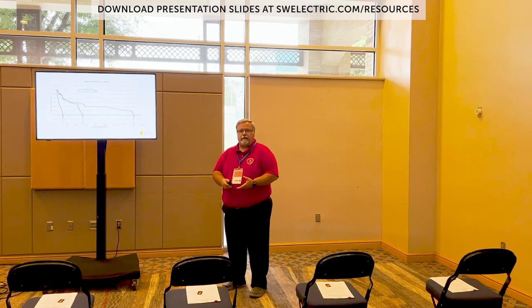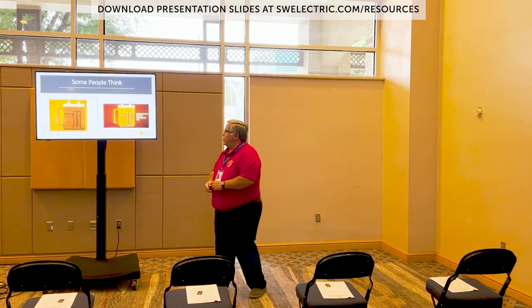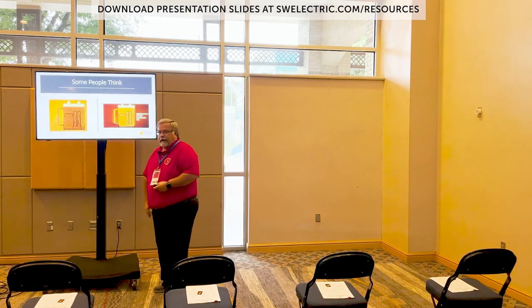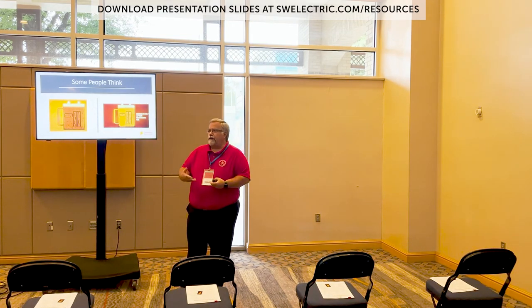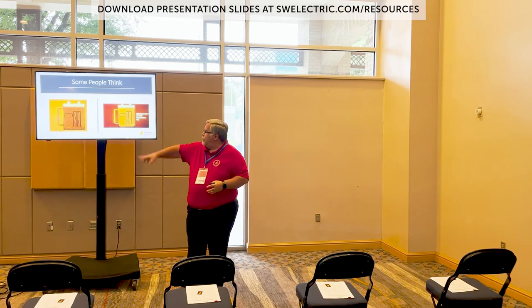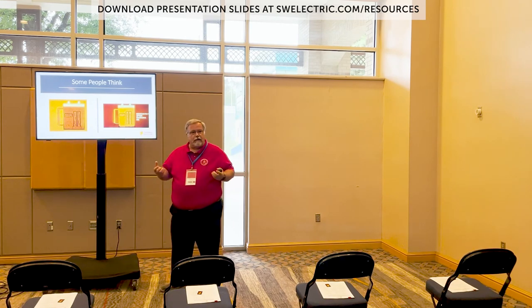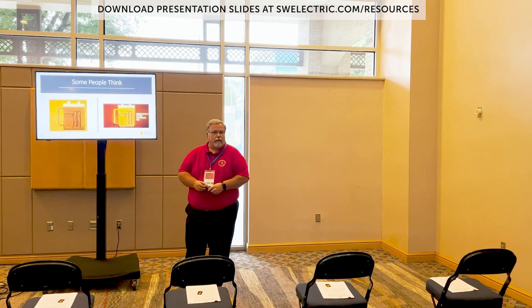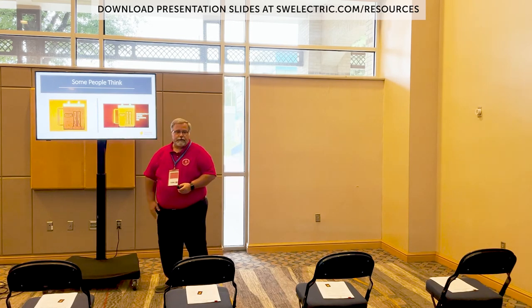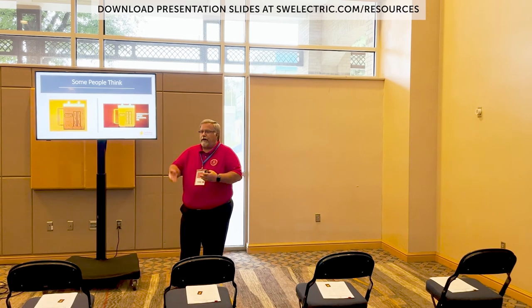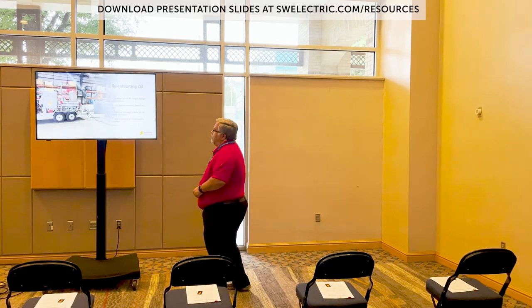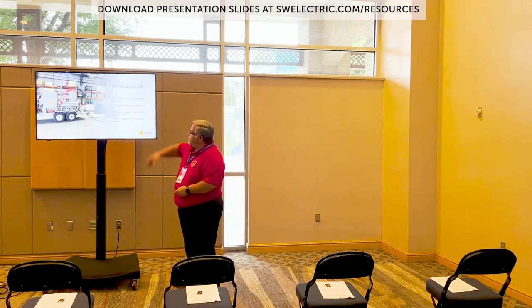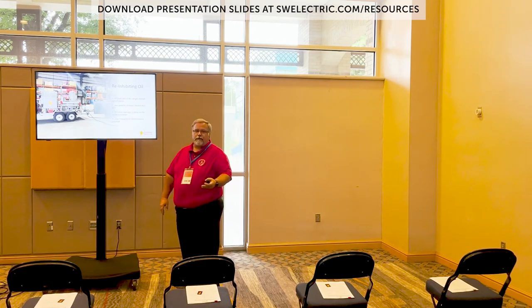And that can be done easily with oil processing. Like I said, there are people that believe that just by taking the old oil out and putting new oil in, you're doing great. But all that stuff that's in your winding is eventually going to leach back out into the oil, and you're going to be right back where you started from. That's why we have to filter it, run it through a Fuller's earth filtering system, heat, vacuum, things like that. Re-inhibit it. We want to keep the test results at acceptable levels, except for the inhibitor content.